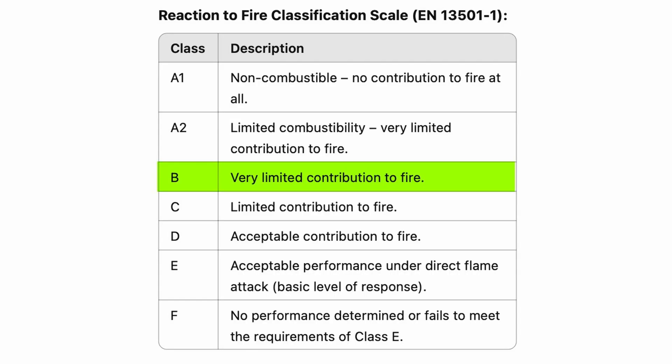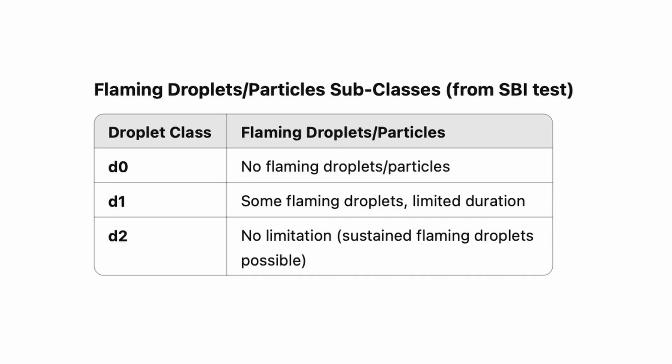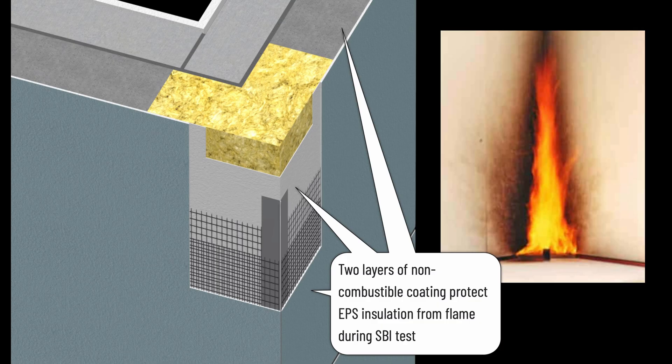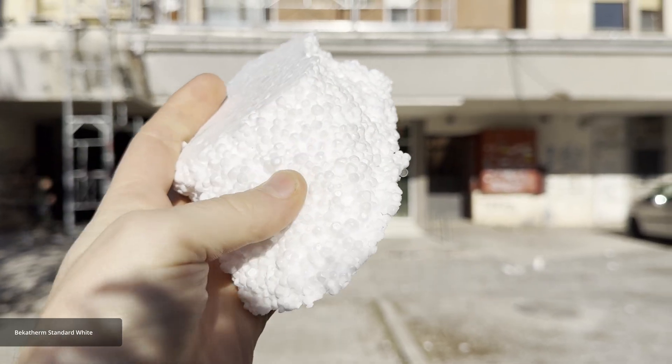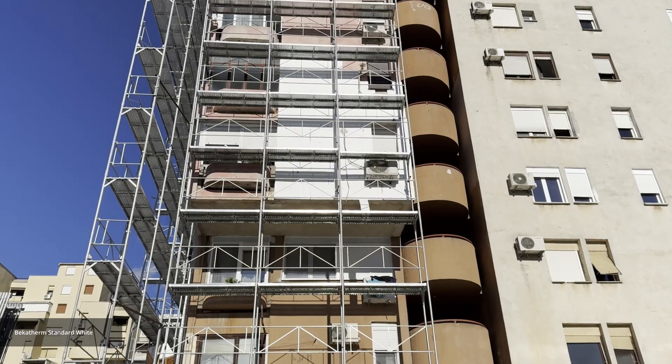The reason is that unlike individual materials, facade systems are classified for their reaction to fire according to a different test — one designed to emulate the reaction of a wall exposed to a small fire like a wastepaper basket in the corner of a room. This test monitors spread of flame from B (moderate) to A2 or A1 (limited combustibility or non-combustible), as well as emission of toxic smoke (S) and production of flaming droplets (D). In the case of a render system, EPS insulation is covered by two layers of cement-based coats which, if exposed to a lateral flame, do not allow the combustible polystyrene to ignite. This allows system manufacturers to classify EPS insulated render systems as B-rated, making them seemingly suitable for high-rise buildings under local building codes — and this is how these systems found their way onto mid- to high-rise buildings in Europe and around the world.